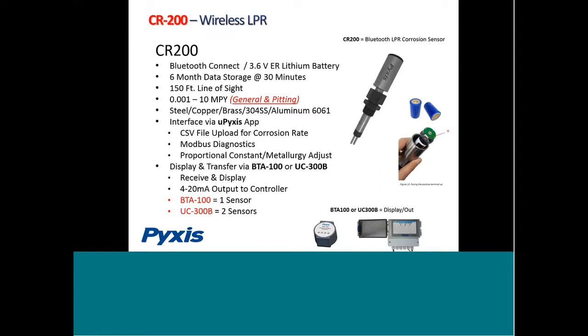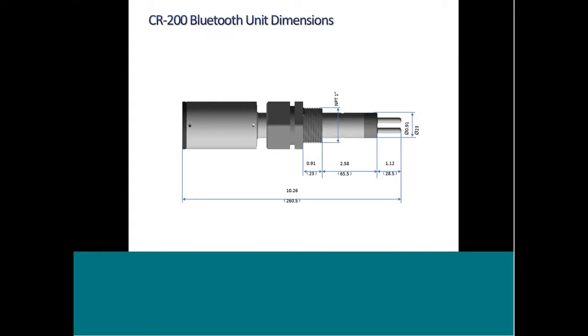That same display in a single channel, one sensor to one display, you would use a BTA100. And in a multiple channel, two sensors to one display, you would use a UC300B. Remember, each sensor is sending out two signals, both general and pitting corrosion. So you're tying up two channels when you send them. It's a little schematic on the CR200. Again, they look nearly identical.